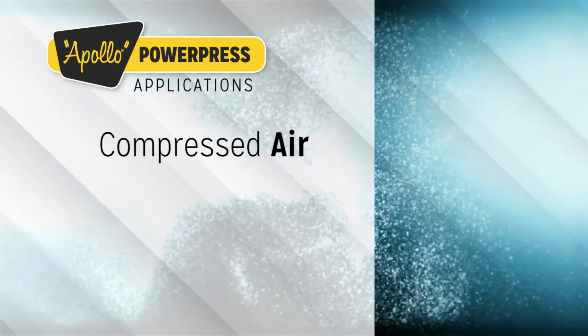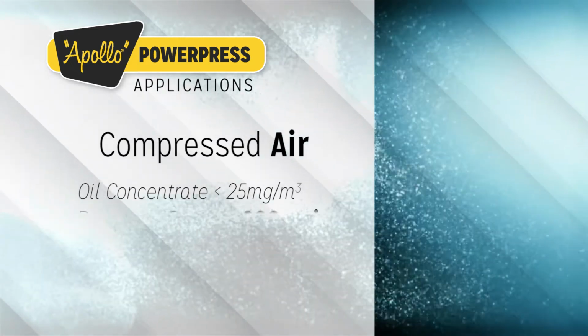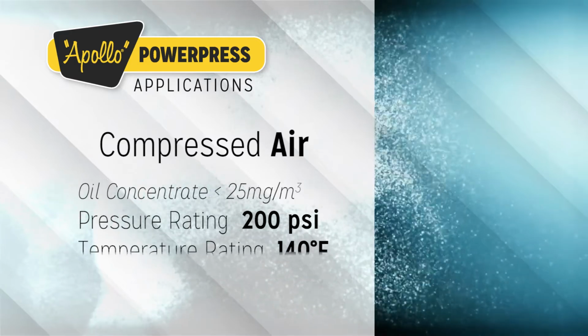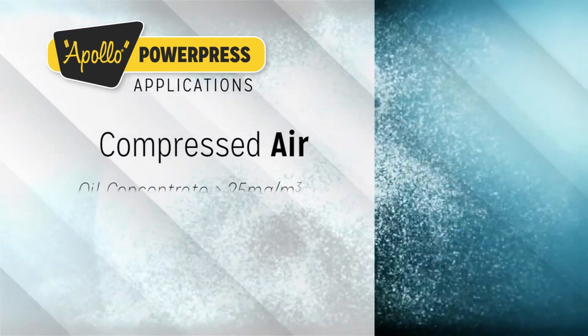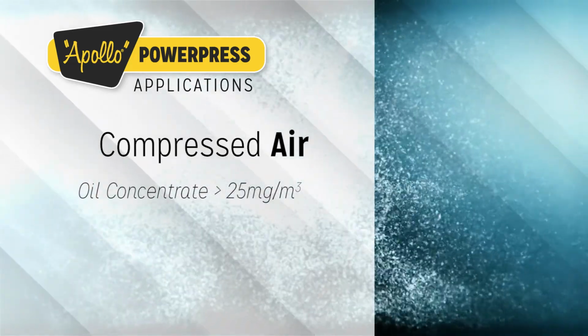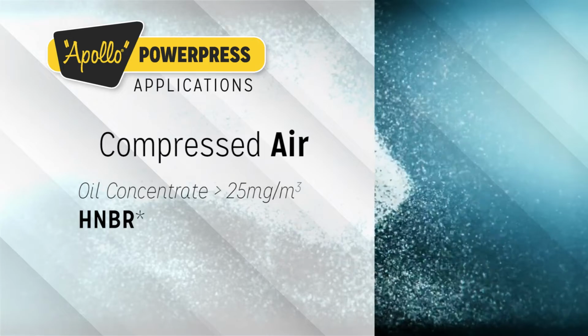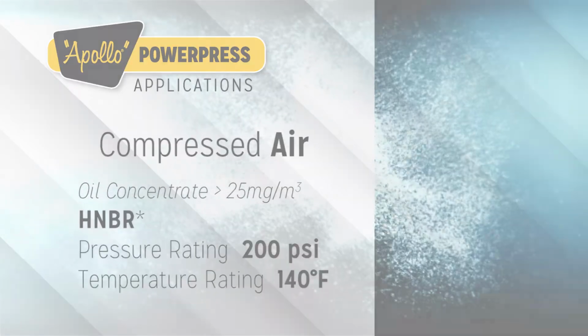Compressed air, with oil concentrate less than 25 milligrams per meter cubed, is rated at 200 psi and up to 140 degrees Fahrenheit. If compressed air has an oil concentrate greater than 25 milligrams per meter cubed, then you must use HNBR at 200 psi up to 140 degrees Fahrenheit.